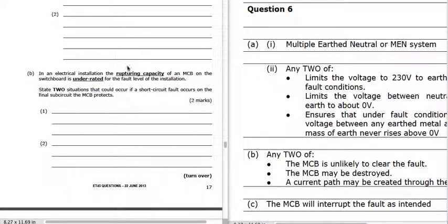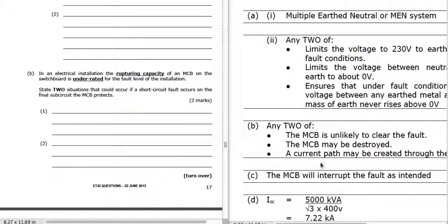If the rupturing capacity of an MCB on the switchboard is underrated, it's not able to break safely under high fault currents. Two situations that could occur if a short circuit fault occurs: the MCB is unlikely to clear the fault — we could get an arc and the fault could be sustained — and the MCB may be destroyed, with a current path created through the MCB.